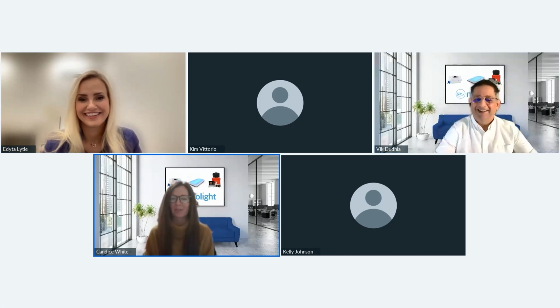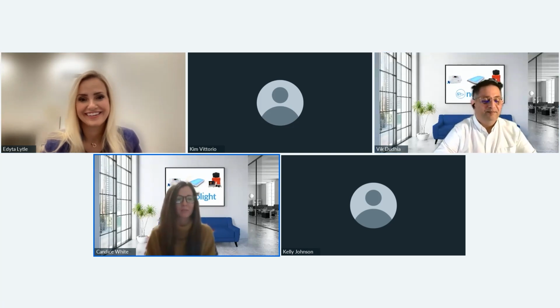Adita knows from the nursing side that we typically see these done either bi-yearly or yearly. And then I think I had mentioned earlier, from a continuing education standpoint, when you're building a new program, you want to get that camera out as often as possible, and you want to practice like you play. We're always telling the new nurses, actually stick the little baby head, the test eye, in a radiant warmer, in an incubator, in a crib, whatever your imaging environment is, and really get used to those small details.